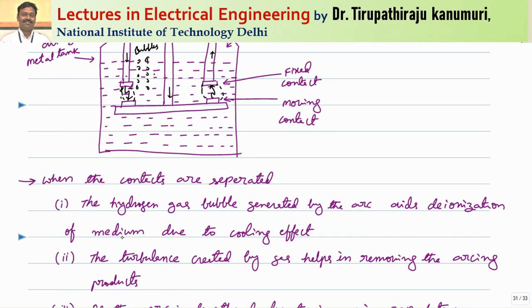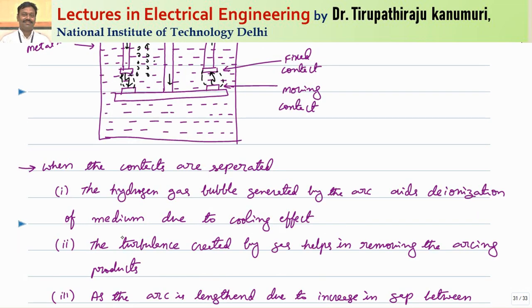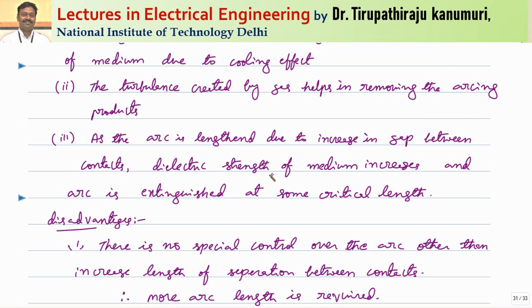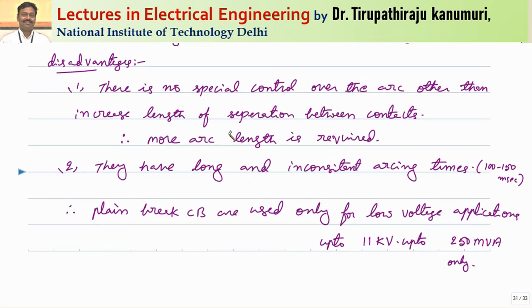Since there is no specific mechanism to extinguish the arc at a shorter distance, more length is required — that is the disadvantage of the plain type circuit breaker. When the contacts are separated, the hydrogen gas bubble aids deionization due to cooling and turbulence, removing arcing byproducts. As the arc is lengthened by the increasing contact gap, the dielectric strength of the medium increases and the arc is extinguished at some critical length. Because there is no special control over the arc, more contact separation distance is required, and the circuit breaker cannot be used for recloser applications.